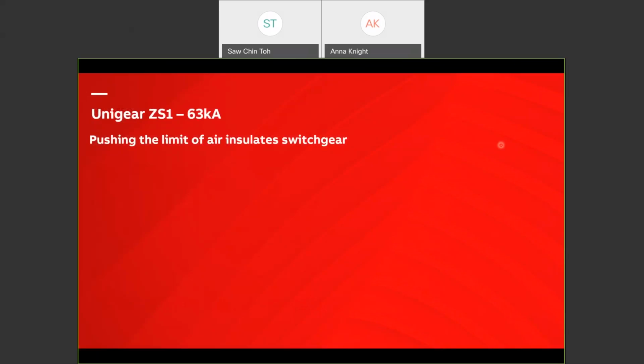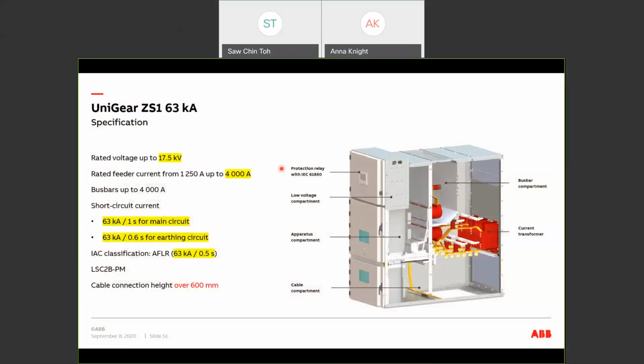Next, another one of our new launches is the 63 kA panel. This is for a very specific application and more commonly used in power stations. We are one of the few manufacturers that can meet such a high rating for such a high-end application. The maximum rating of the cubicle is 17.5 kV, 4000 amps. The short circuit current withstand for the main circuit is 63 kA 1 second, and for the earthing circuit is 63 kA 0.6 second. Internal arc classification is AFLR 63 kA 0.5 second.